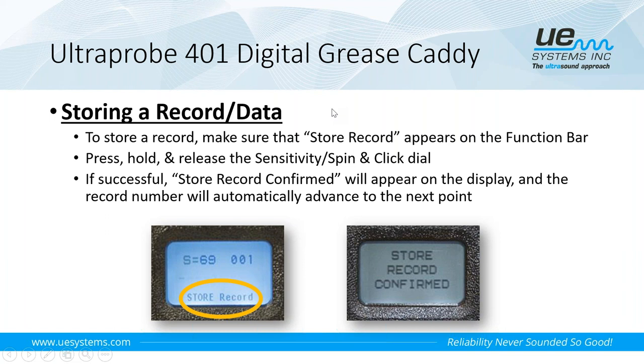All right, so then storing a reading or storing a record. We've already talked about this previously, but we want to make sure we go down to the function bar. Using the sensitivity spin and click dial, we navigate down to the function bar. Once the function bar is blinking, we scroll left or right using the sensitivity dial until we see store record. Once we've got a decibel level on the display and we're ready to store a reading, we simply press and hold the sensitivity dial. Then we'll see store record confirmed, and the grease caddy will automatically advance forward to the next point. So we've just stored a reading on that point.